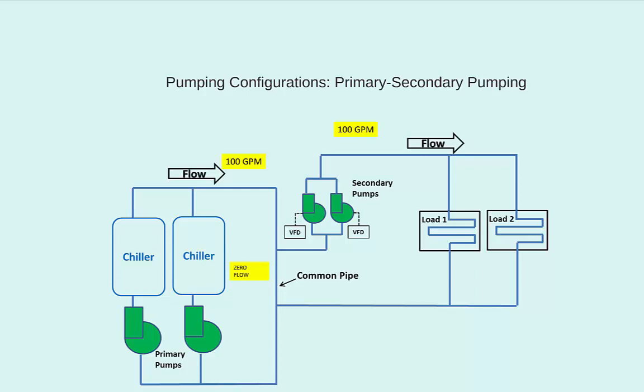Say the coils keep calling for more and more flow. Then there may be an instance when the flow is going upwards through the common pipe. That would be a good indication for an additional chiller and corresponding primary pump to turn on and make additional chilled water available to the secondary pumps, which in turn they can send to the coils. There are different ways in which these chillers are staged on, and such control sequences will be discussed at length during the primary equipment staging lesson of this module, as well as during the low delta T syndrome lesson of module 3. So that is the primary-secondary pumping configuration.